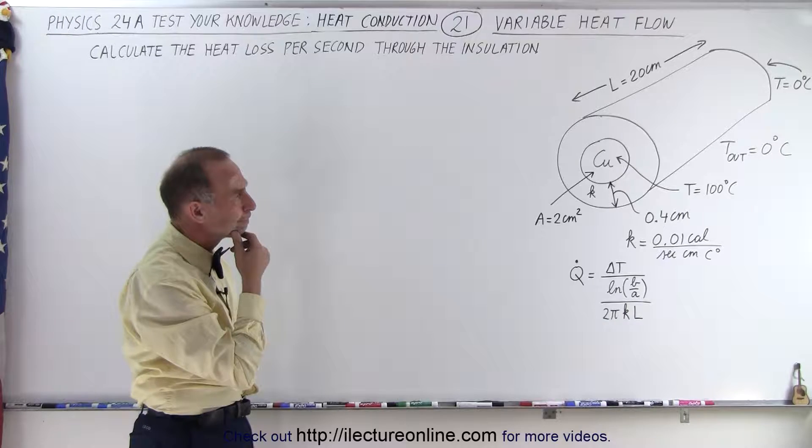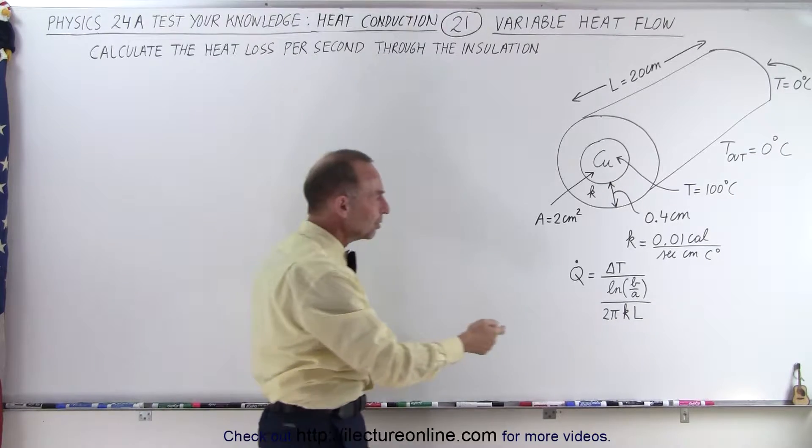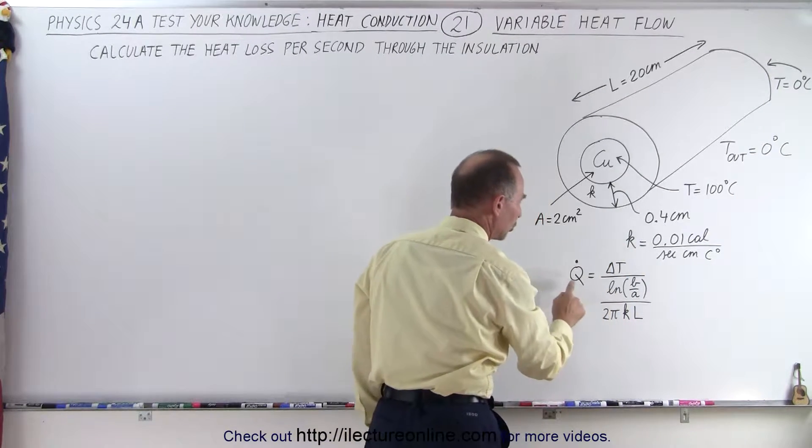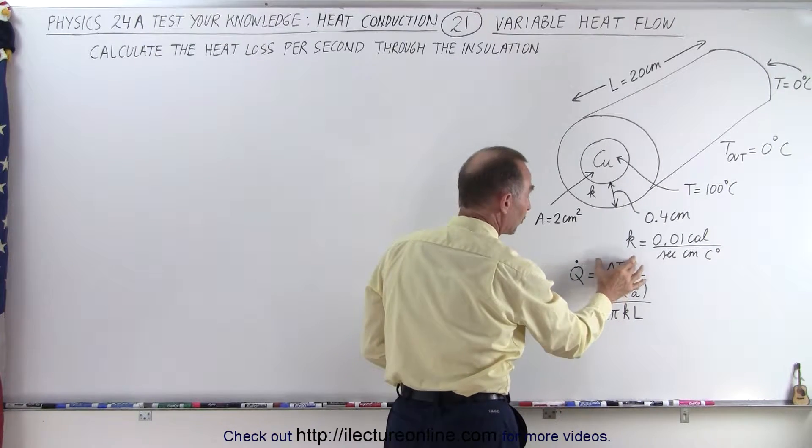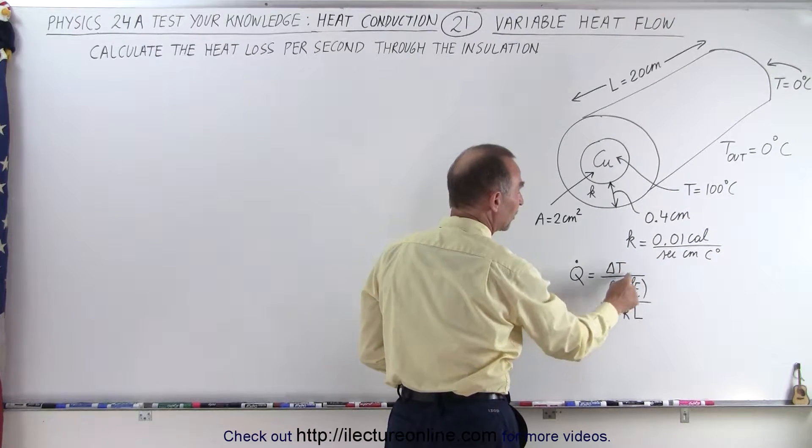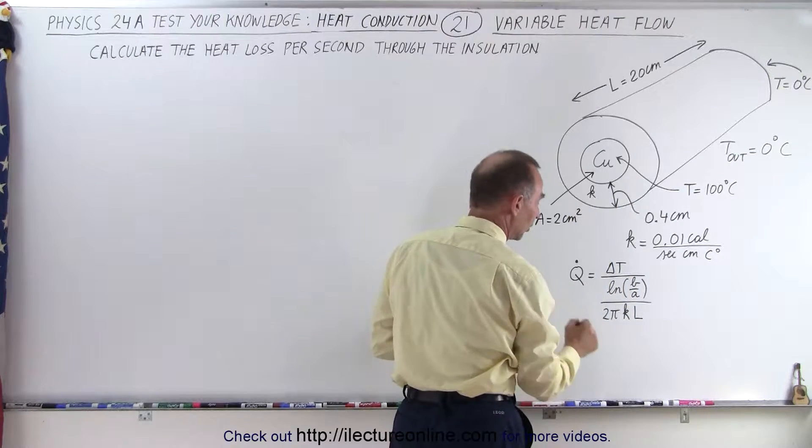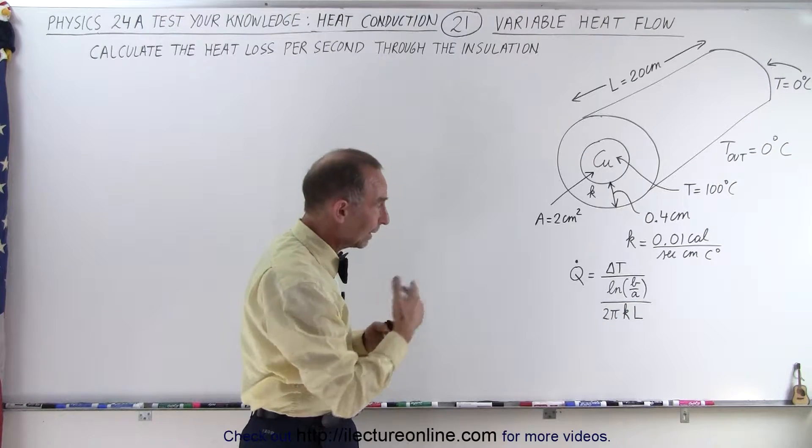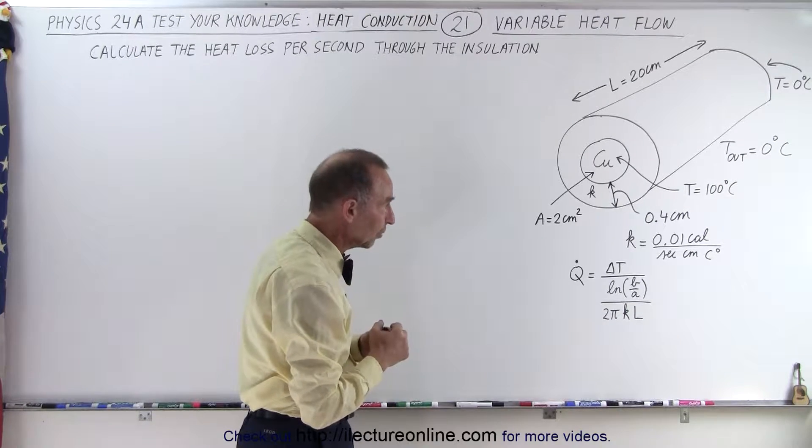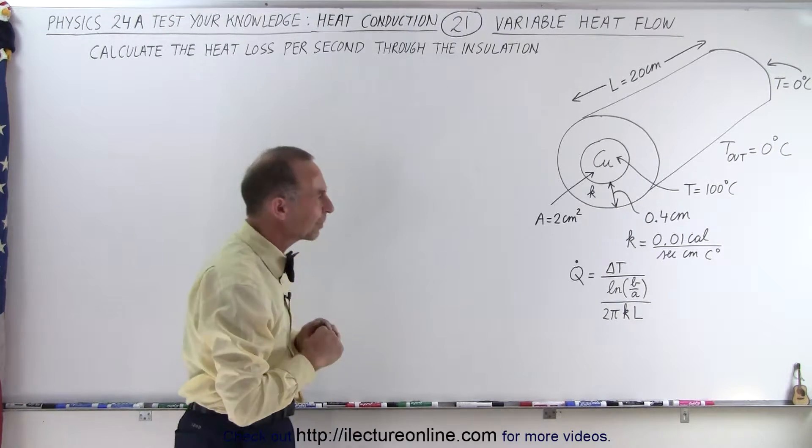How do we do that? Well, starting with the original equation right here where Q̇, considering that it's constant, is equal to the difference in the temperature divided by the natural log of B over A through the insulating material, divide that by 2πKL, L being the length of that and K of course being the constant, the conductivity constant of the insulating material.